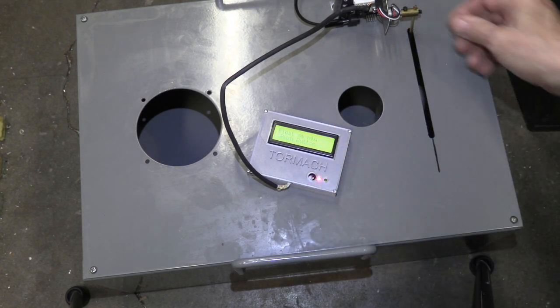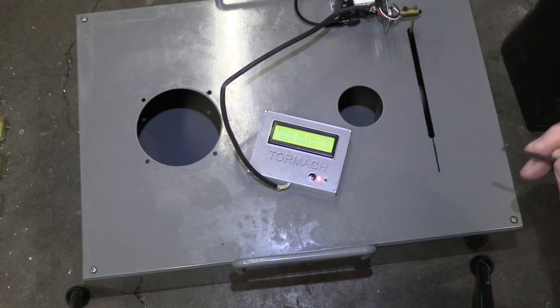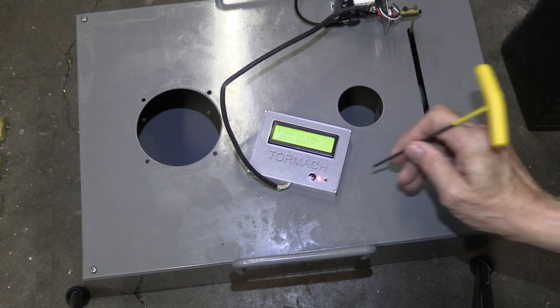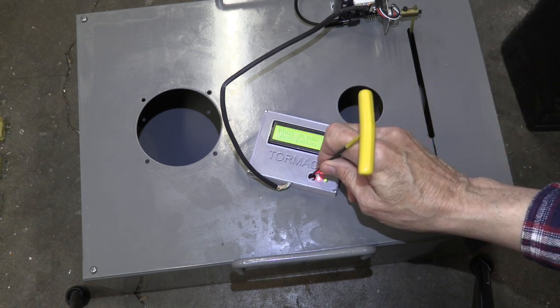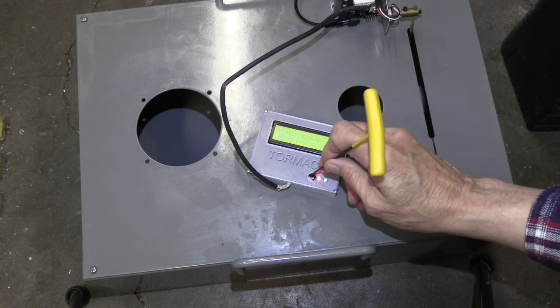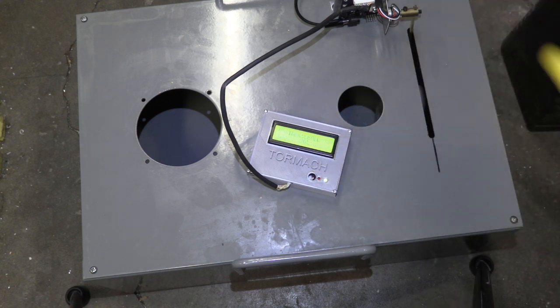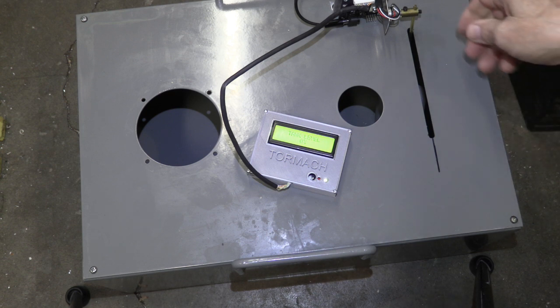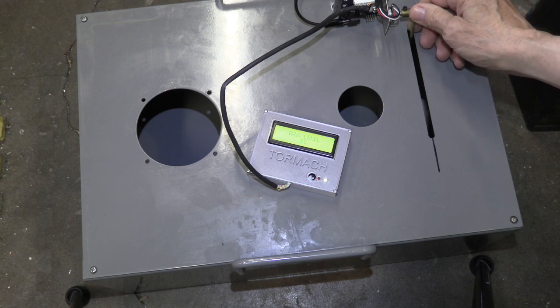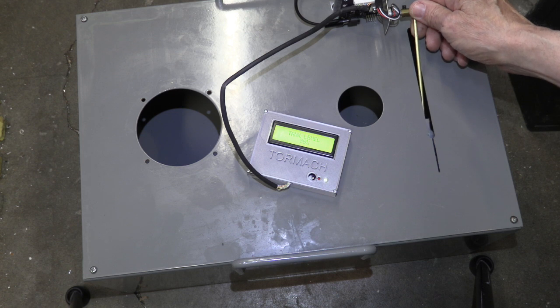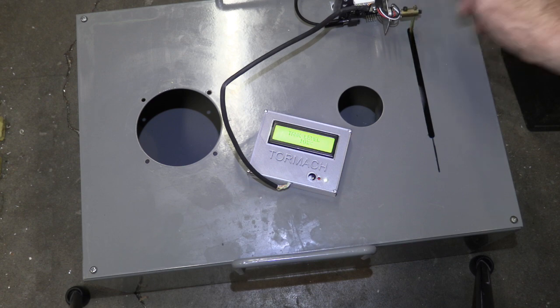Now it says put the float at minimum, which I just let drift down so the float just sits on the bottom of the tank, and we'll push the button one more time. Okay, it says the calibration is okay. Push the button one more time. Let the system reset, and it shows that the level in the tank is 0. And from this point on, the system will indicate the level in the tank, which corresponds to the position of the float, from 100% to 0%.